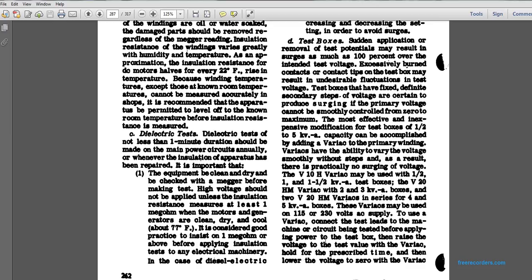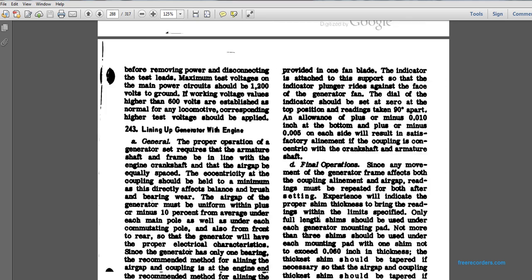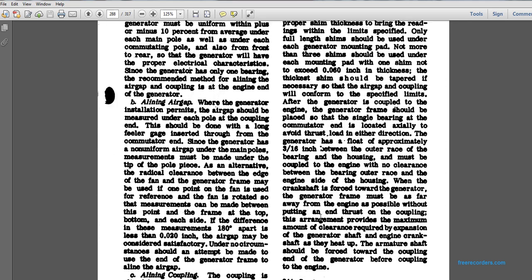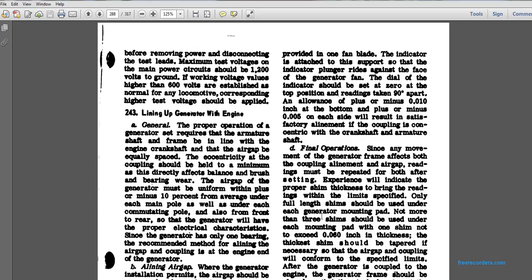To use these variacs, connect the test leads to the machine circuit being tested before applying power to the test box. Raise the voltage to the test value with the variac, hold it for the prescribed time, then lower the voltage to zero with the variac. Before removing and disconnecting the testing leads, note that the maximum test voltage on the main power circuit should be 1200 volts to the ground. If working voltage values higher than 600 volts are established as normal for any locomotive, a correspondingly higher testing voltage should be applied.